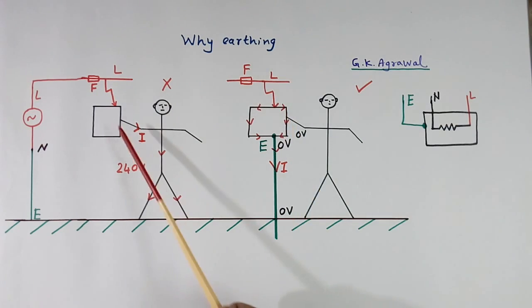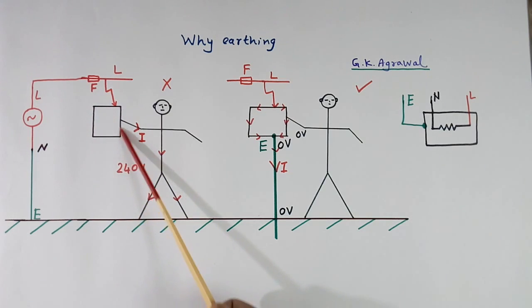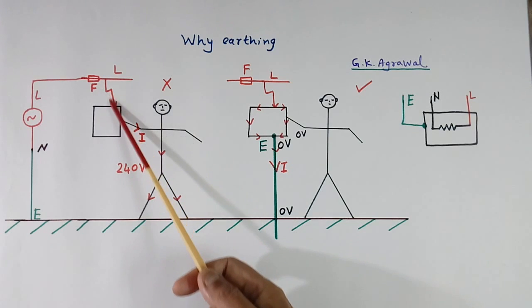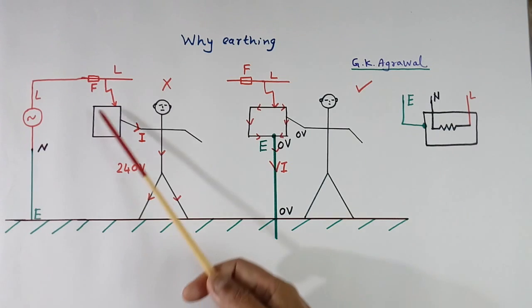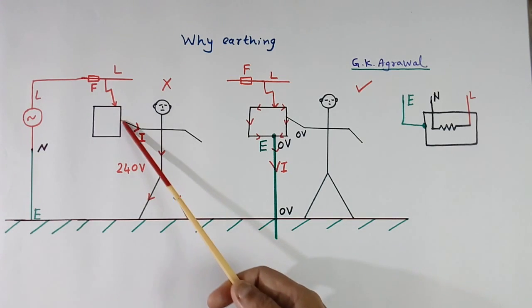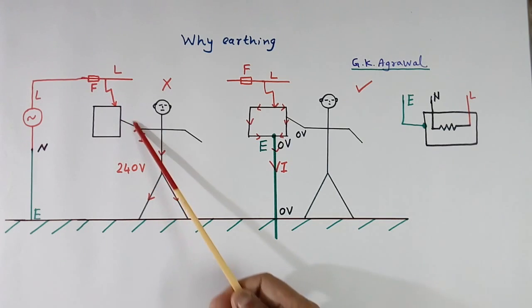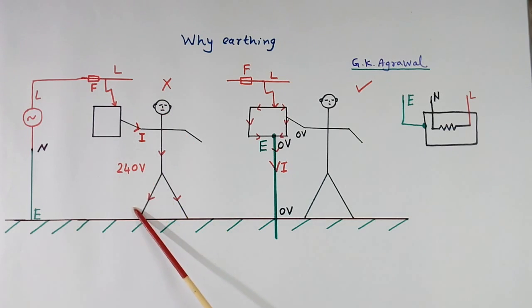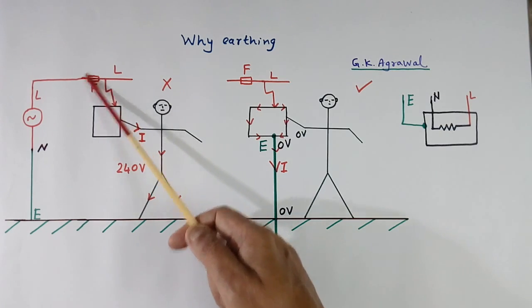Now why earthing at the load side? I have shown one electrical equipment — say an oven or heater. And we are touching this, and somehow there is a fault. So because of the fault, current will flow through our body. The circuit is complete and we get a shock because current is flowing through our body. Our body resistance is more, so even though full 240 volt comes, current flow will be less — the shock will be there. But this current may not be sufficient to blow the fuse.